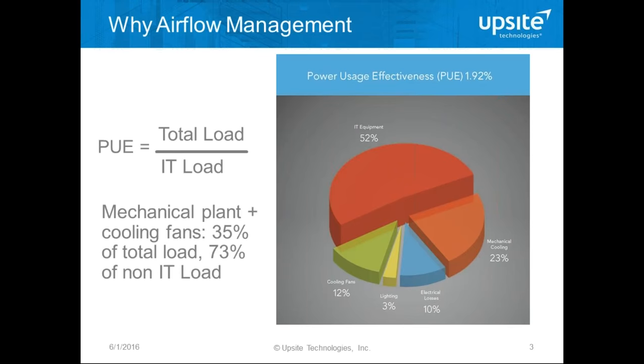PUE stands for power usage effectiveness and it's a very simple metric to calculate — the total load of the entire data center divided by the IT load. Mechanical cooling and cooling fans represent 35% of the total load and 73% of the non-IT load, in strong comparison to electrical losses being only 10%. There's a lot of effort being made to improve efficiency of infrastructure, and while looking at UPS efficiency is a good idea, it has a relatively small effect on the total equation.